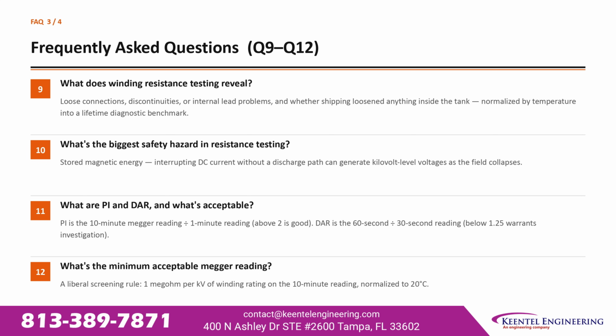What are PI and DAR, and what's acceptable? Polarization index is the 10-minute Megger reading divided by the 1-minute reading, where above 2 is good. Dielectric absorption ratio is the 60-second divided by the 30-second reading, where below 1.25 warrants investigation. What's the minimum acceptable Megger reading? A liberal screening rule of 1 megohm per kilovolt of winding rating on the 10-minute reading, normalized to 20 degrees Celsius.